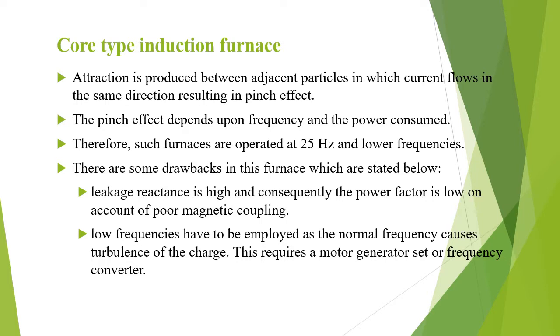In this furnace, there is pinch effect developed because of the attraction produced between the adjacent particles in which the current flows in the same direction. This pinch effect depends upon the frequency and the power consumed. So these furnaces are operated at low frequencies, around 25 Hz. There are few drawbacks in this furnace. The leakage reactance is high, and also the power factor is low due to poor magnetic coupling. Low frequencies have to be employed because the normal frequency causes turbulence in the charge. This requires a motor generator set or frequency converter.